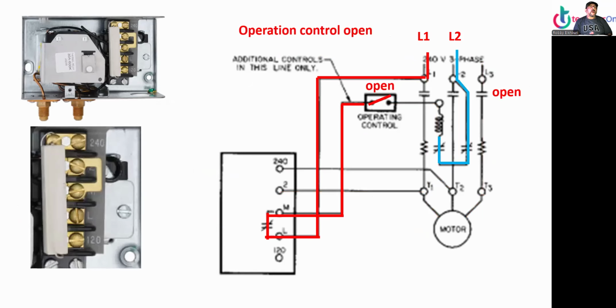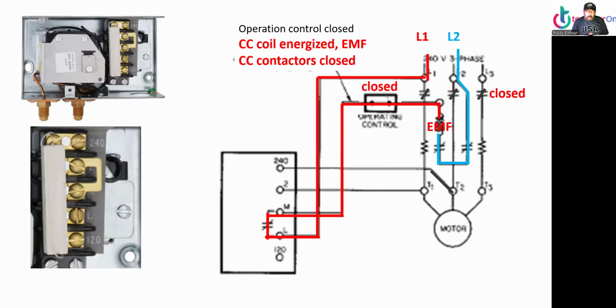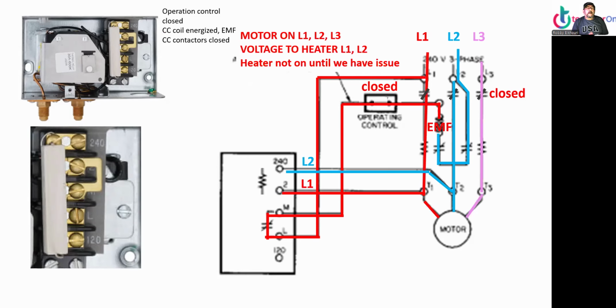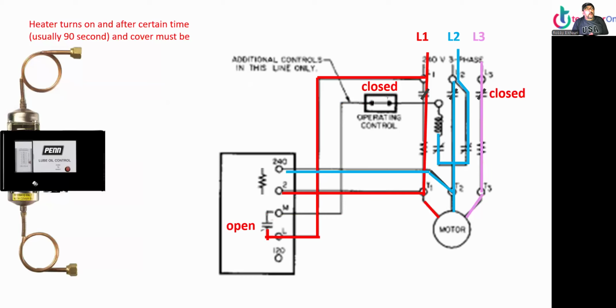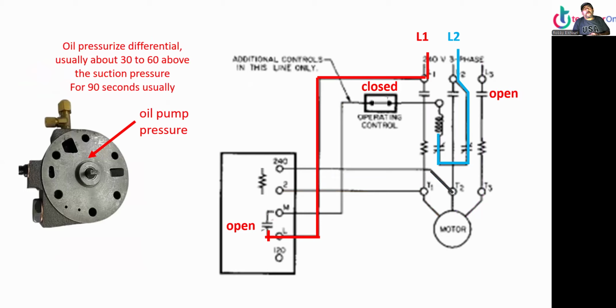But we'll go one by one. All right, so normal operation, right now the system is off. Power comes in at L1 through the oil control, a normally closed switch between M and L, but it does not turn on the motor because the operation control is open. Now, calling for cool closes it. We have power to the compressor contactor coil, which creates a magnetic field and closes the switches. Now we have power L1, L2, L3 to the motor, and L1, L2 going to the heater in the oil control. Now, if we have a problem with the oil, the heater turns on after a certain time, usually 90 seconds, but the cover must be on, because if you take off the cover, that heater will never get hot and will never work. Then oil pressure differential is usually about 30 to 60 above suction pressure, for about 90 seconds. That's the oil pump pressure.